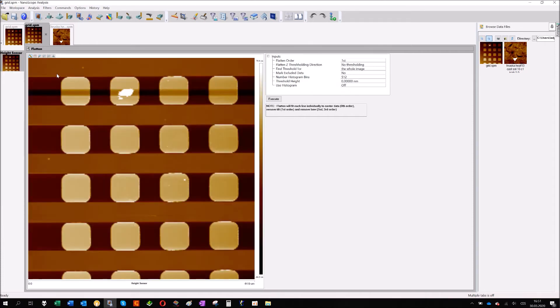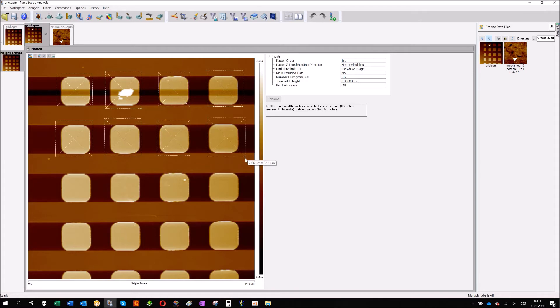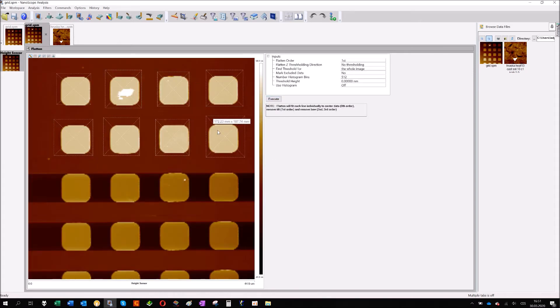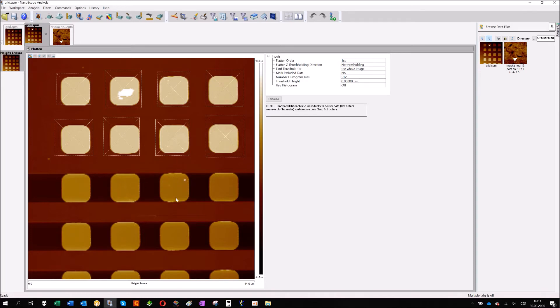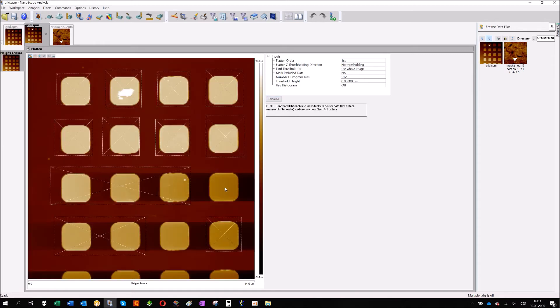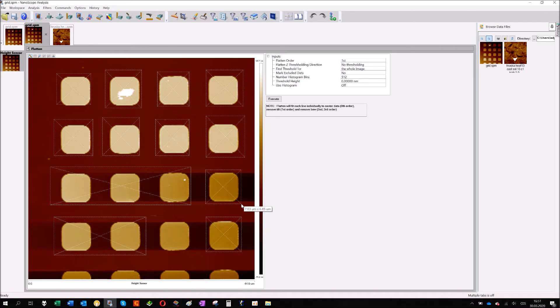The same we can do here. We just need to mark each parameter and just go step by step. And you can see it works. It's very common mistake. Based on the position of your feature on the image, it can change the effect. For example this one, and you can see it's changing and making this kind of lines. If you will see this kind of lines on the AFM image, it means somebody doesn't know how to use correct flattening for the imaging. Don't do that.